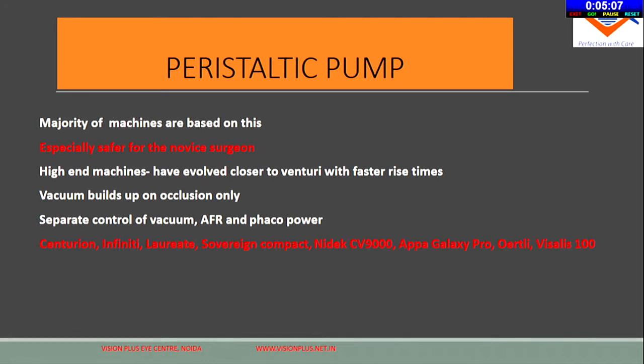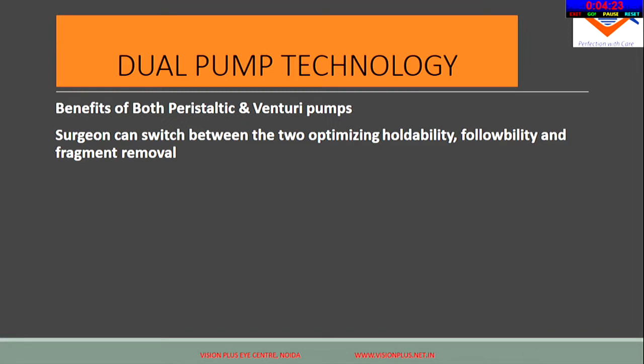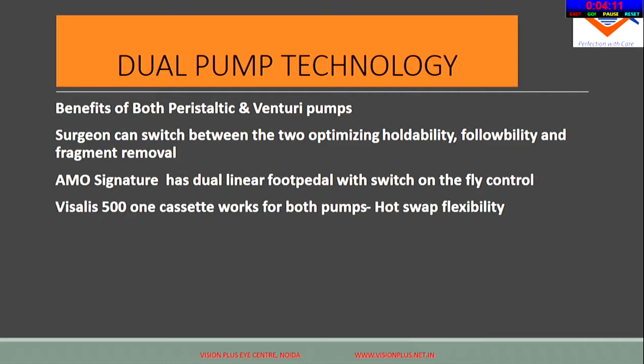Some machines with a peristaltic pump include the Alcon platforms, the Sovereign, Nidek, and Appa. If you are planning to upgrade, go to each manufacturer at the conference and understand in depth what options are available. The venturi pump is much faster — vacuum is produced by compressed air or gas and is instantaneous — though there is a greater risk of inadvertently catching the iris or posterior capsule. The Stellaris, Visalis 500, and Constellation are venturi-based systems. The dual pump technology in the AMO Signature Pro offers benefits of both peristaltic and venturi, allowing you to switch between them.